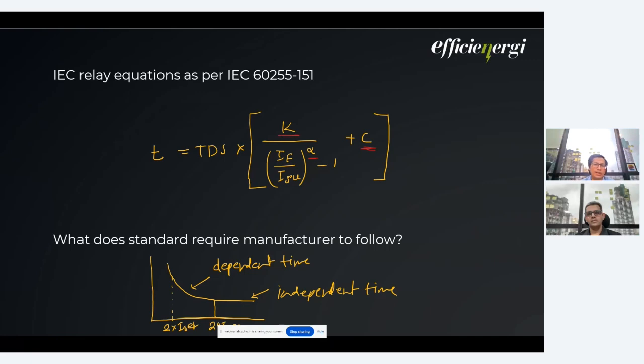Then we have the equations given by the IEC. The IEC relay equations are as per IEC 60255, specifically for overcurrent relays. T is the time of operation, which depends on the TDS, the time dial setting. Sometimes we also use TMS, time multiplier setting. Then there is a constant term K. Then there is the fault current and the pickup current, the set value of the current, raised to the power of alpha minus 1, plus C.